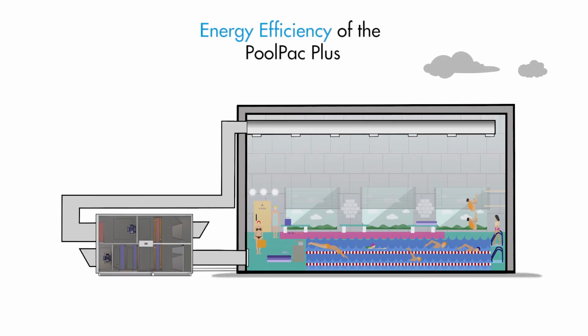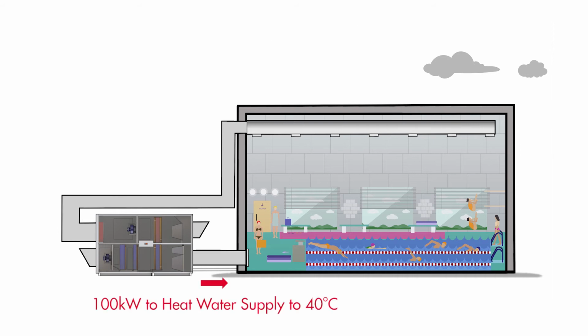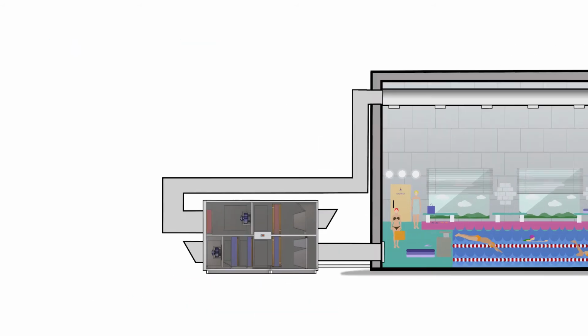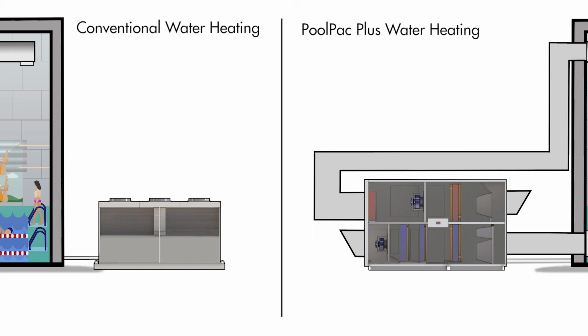To explain the efficiency advantages of the PoolPac Plus more clearly, let's go over a hypothetical example. Let's say a pool water heating system needs to provide 100 kilowatts to warm the water to 40 degrees Celsius. And the temperature outside is 6 degrees Celsius, while the indoor space temperature is 28 degrees Celsius. With a conventional system, the DX heat pump will be trying to absorb heat from the 6-degree ambient air, and to do so, its evaporating temperature will need to be very low, something like -5 degrees Celsius.